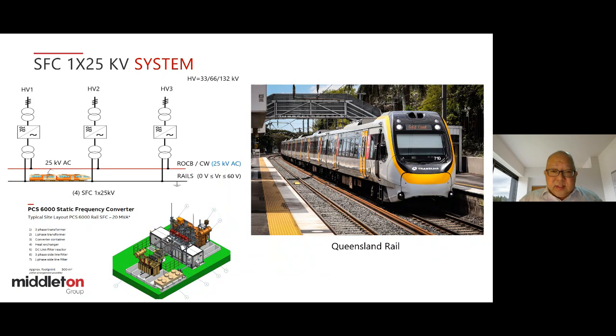Now we come to a new technology here, the static frequency converter. So using rail return, this system is 1 times 25 kV AC using rail as the return conductor. In Australia and the UK, we have 3-phase high voltage going in at 50 Hz and 1-phase, single phase, 25 kV out, also at 50 Hz. And of course, in countries like Germany, Austria, Switzerland, Norway, and Sweden, they have 15 kV out and 16.7 Hz instead of 50 Hz.